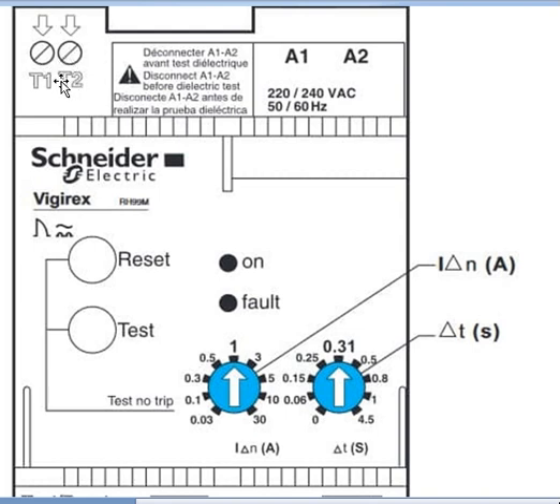If there is any fault in the circuit, the leakage current will flow in the earth wire, and there will be some difference in the current. The toroid is going to sense the current and will give a signal to T1 and T2, and your relay is going to trip the circuit. So friends, this is how an earth leakage relay works.